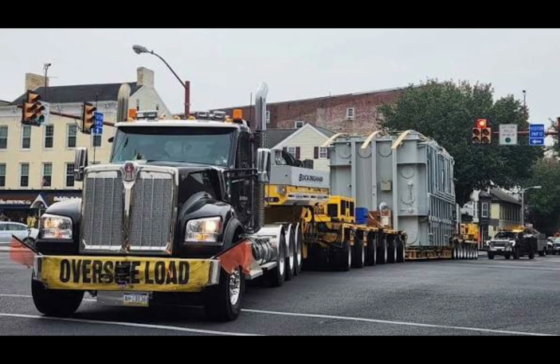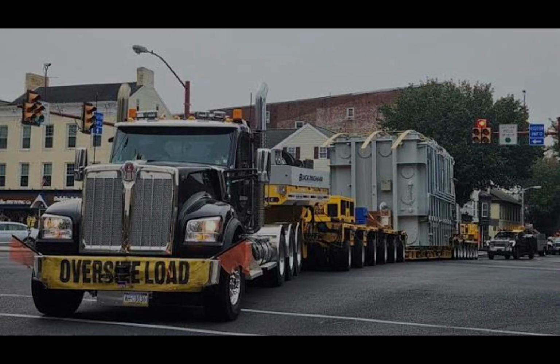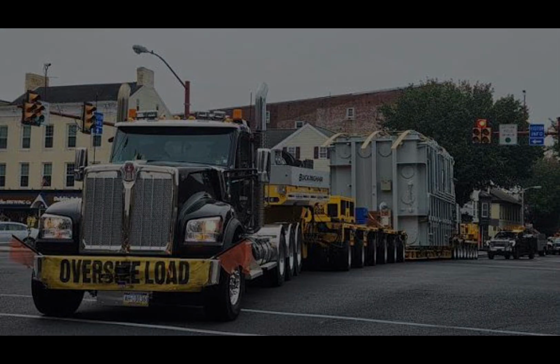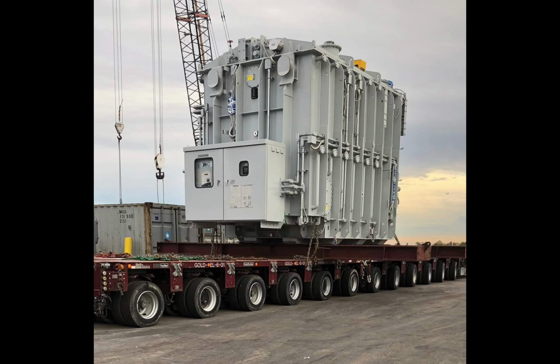Stepping down voltage is only half the battle. A substation is also the grid's immune system. Imagine a Category 4 hurricane sweeping through Florida, throwing a massive oak tree across a 230 kilovolt transmission line. The moment that tree bridges the gap between the wire and the earth, thousands of amps of fault current rush toward the grounding point. If this massive surge travels back to the substation, it will detonate the power transformer in a catastrophic explosion. To survive this, the substation must detect and isolate the fault in milliseconds.